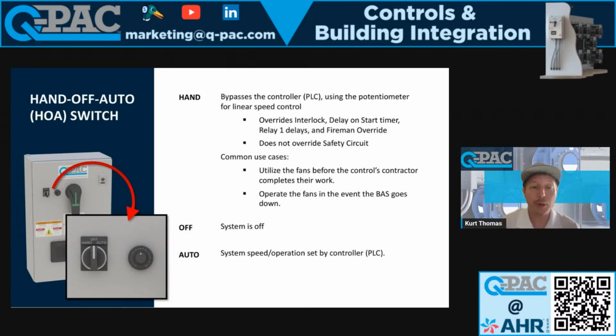If you do put it in hand mode, you are going to bypass several features, right? Since we are bypassing that PLC, that means that your Fireman Override is going to be bypassed, your Interlock is going to be bypassed, any delays that you have set up will no longer function in hand mode. So it's purely, hey, I'm going to put it in hand mode, bypass everything, and turn that potentiometer to get the fans running. There is one thing it does not bypass, however, and that is your safety circuit. So if you have your high stat, low stat, any type of safety sensors, hand mode will shut off, or your fans will shut off if any of those sensors trip. So just know that. And we'll talk more about the safety sensor or the safety circuit a little bit later.